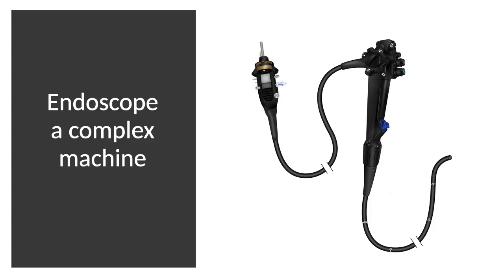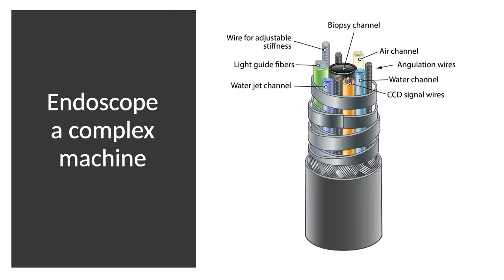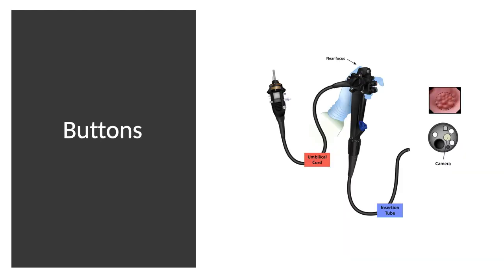And when you look at the scope, it is a very complex machine which has multiple small channels that can take air or water, that can suction fluid or air. It can take cables of light and images back. And finally, there are different wires to allow the scope to be like a noodle and twist and go around the bends of the gut. And there are lots of buttons that control different functions of the scope. And these buttons have seals that could become leaky and cause problems.